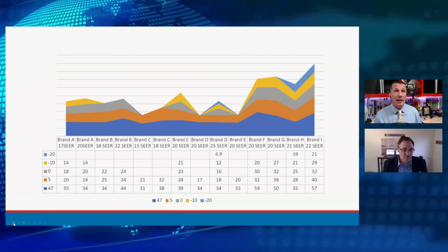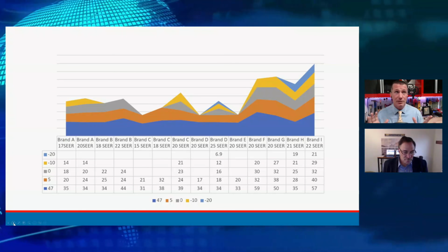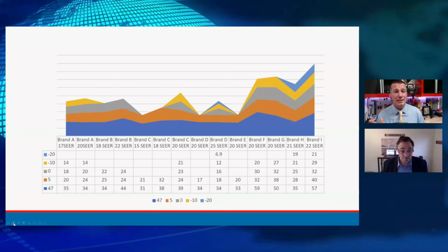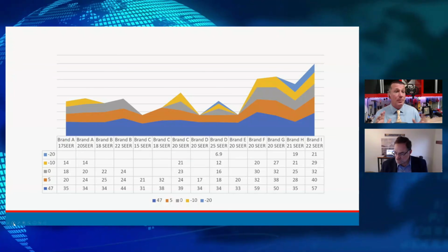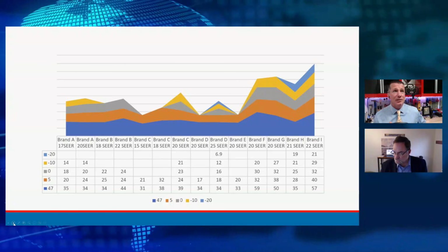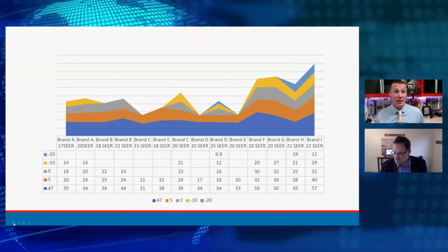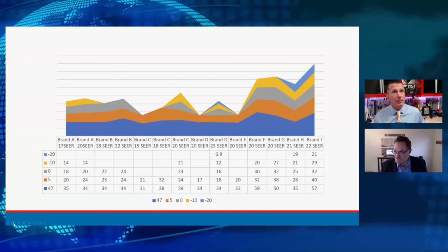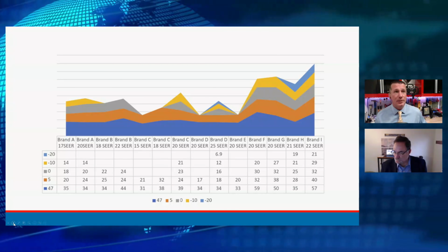That particular brand, they're 18 SEER. Now, a lot of these SEER ratings were from 2022, so some of this is going to change in 2023 as our equipment is being recertified. May or may not, depends on where it landed in that chart. So if we look at that 18 SEER in that third row, that thing is producing a lot of heat at 0, but it doesn't go below 0. And that was an 18 SEER piece of equipment.